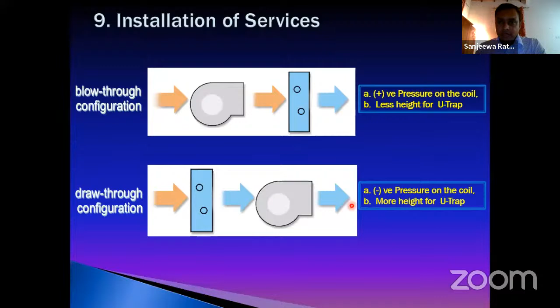Call it blow-through. That means in the coil there is a positive pressure, so we can use a lesser height of the U-trap. But most commonly you will find the draw-through type, where you need a bigger height for the U-traps. So we have to consider this when constructing the concrete plinth for these AHUs. It is an important factor to consider, this height of the U-trap also.